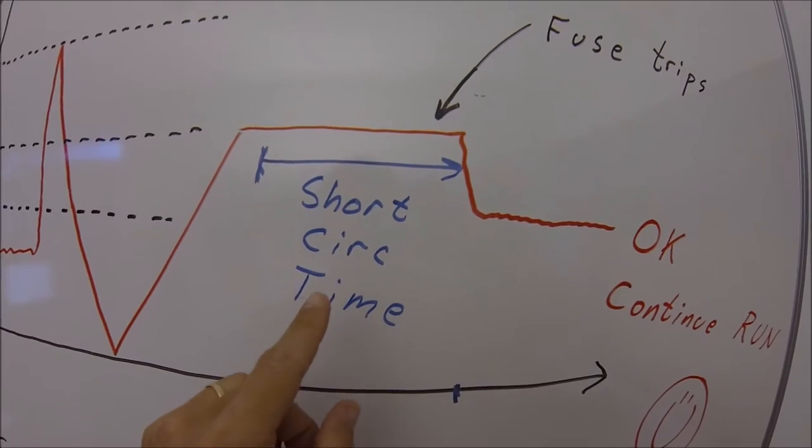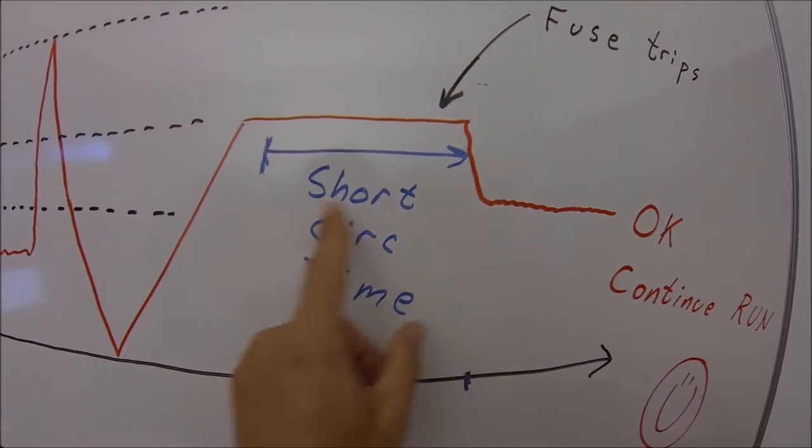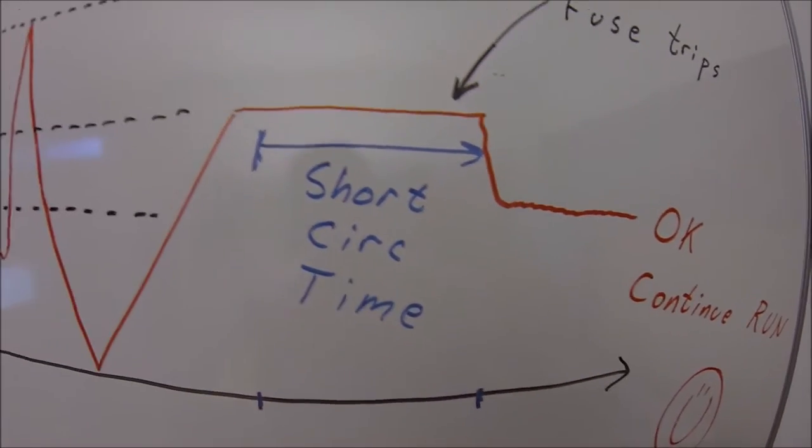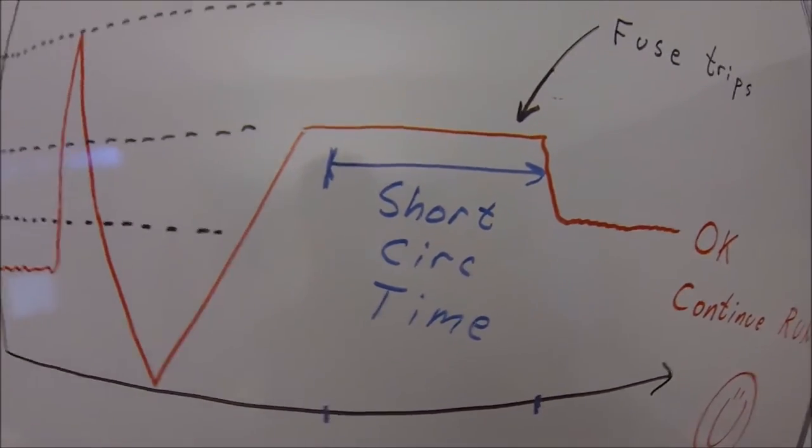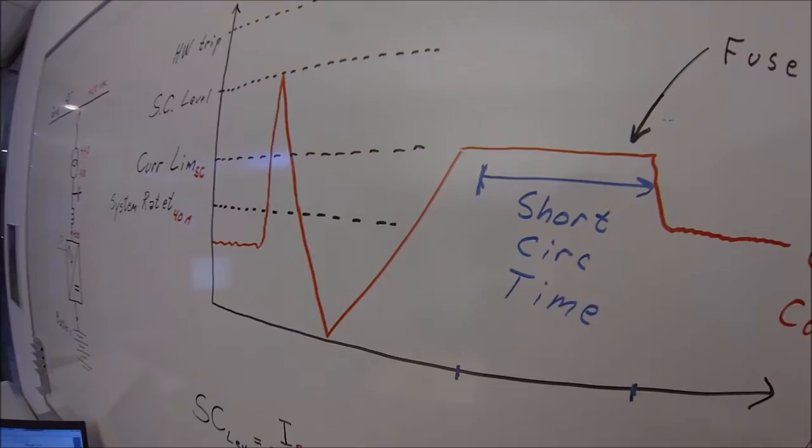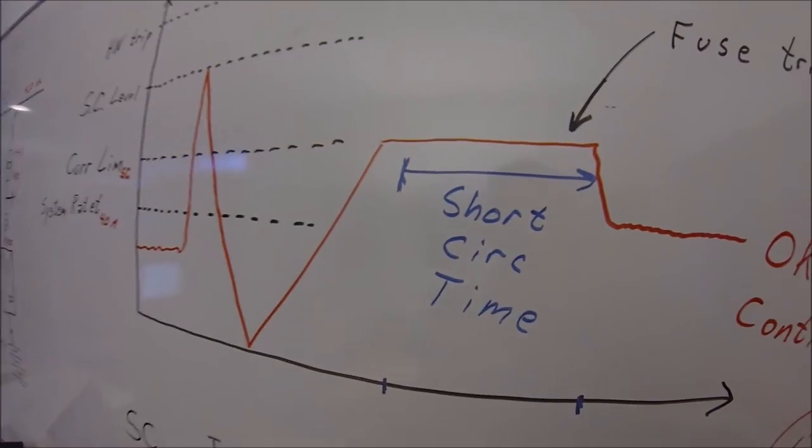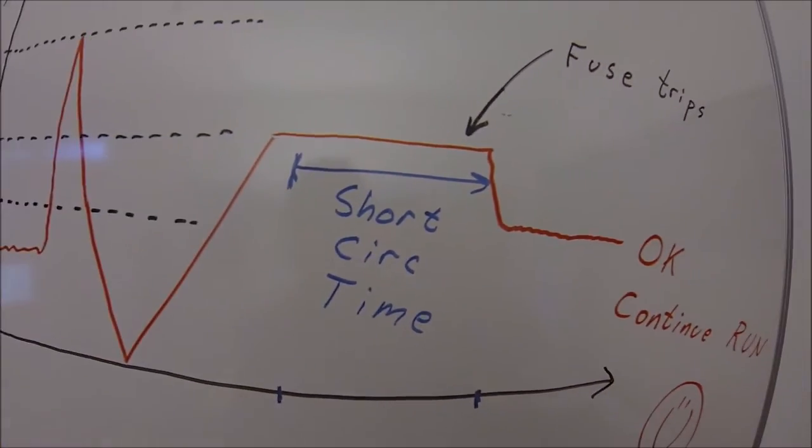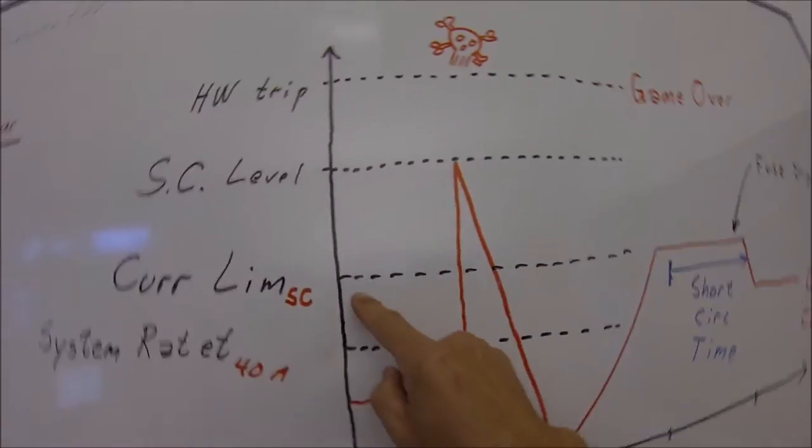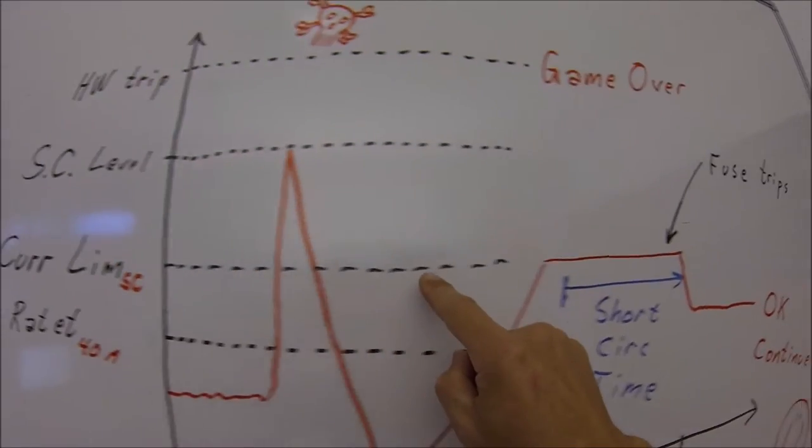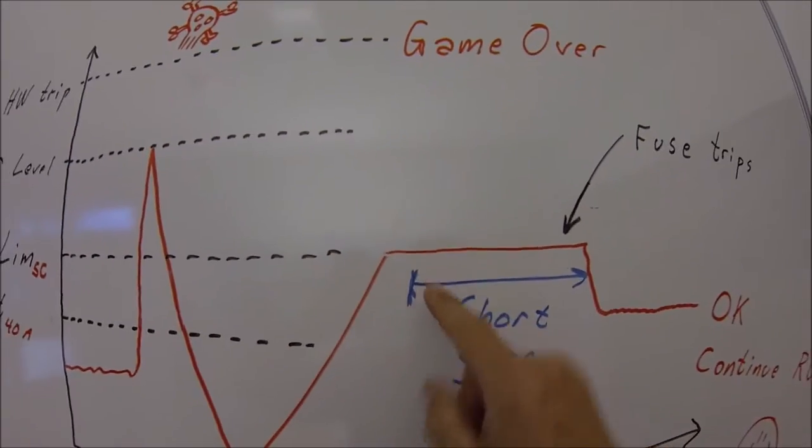We can decide to go up to the current short circuit level and we can sit there for a defined period of time. It could be two seconds, three seconds, four seconds, depends a little bit on the performance of the drive, what type of drive it is. Then we know that we have a known current for a known amount of time.